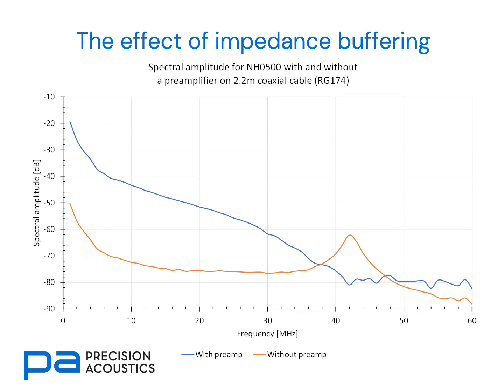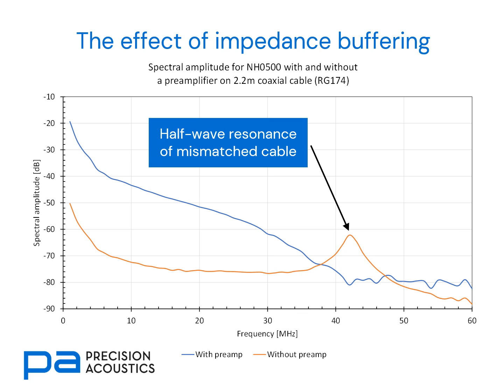If we look at some real devices, we can see just how important this impedance buffering effect is. This graph displays two traces with the same hydrophone connected to a similar length — 2.2 metres — of standard coaxial cable. In the blue trace, we can see what is measured from a broadband acoustic source when we have a preamplifier present. In the orange trace, we see what happens when the hydrophone connects directly to the cable with no preamplifier. We can clearly see there is a 20 to 30 dB reduction in signal amplitude over most of the range, although beyond 40 megahertz this seems to swap over, as we see there's a half-wave resonance from the mismatched cable, giving us an erroneous signal.